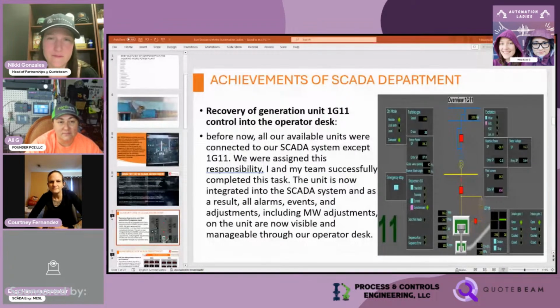In the SCADA department here, we've had some achievements. The first of our achievements this year is the recovery of one of our generation units, 1G11, control, into the operator desk. Before, the control operators in the control room were not able to monitor or supervise this unit. All our available units were connected to our SCADA system except this unit, 1G11. The SCADA department was assigned this responsibility, and my team members and I successfully completed this task. The unit is now integrated into the SCADA system, and as a result, all alarms, events, adjustments, including megawatt power adjustments on the unit, are now visible and manageable through our operator desk.